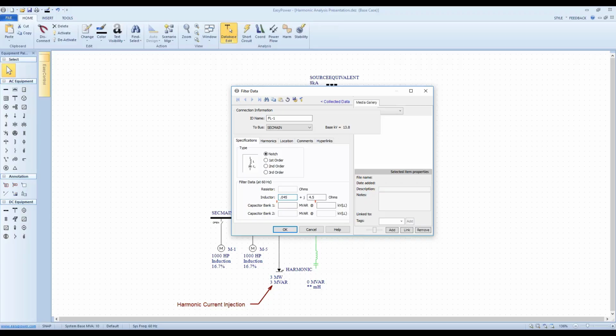Air core reactors have more conductor within them because they have to form that inductance in air rather than with the iron core and gaps within the iron core. So there's much more conductor utilized in an air core reactor, and as such, the resistance goes up. For air core reactors, we typically use an X over R of 60. So 60 for air core and 100 for iron core would be my starting point.